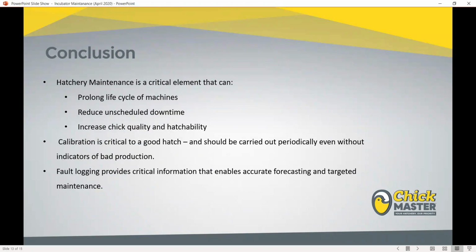Conclusions. So hatchery maintenance is critical. It can prolong the life of your machines, reduce unscheduled downtime, and increase your chick quality and hatchability. Calibration is critical to that. It's critical to a good hatch. It's critical to your hatchery. It should be carried out periodically, even without indicators of a bad production. It allows you to capture those faults before they're a problem. And fault logging provides critical information that will enable accurate forecasting and targeted maintenance.